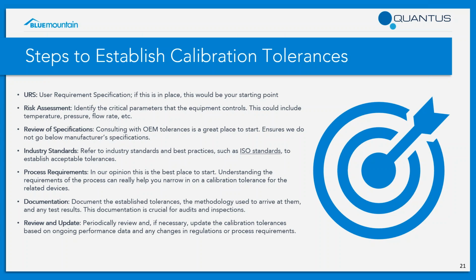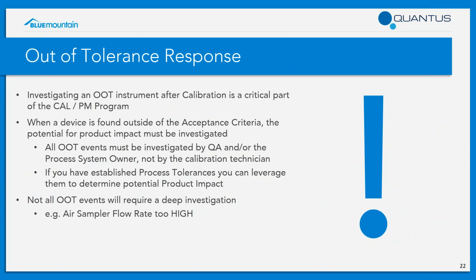If you don't have a URS or a process tolerance, have a discussion with your manufacturing team or the end user to understand where they're using that instrument and where you would calibrate it, because you do want it to be greater than the manufacturer's specified accuracy. Yeah, absolutely, Chris. That's a really good point. And as instruments are getting better and better coming from manufacturers, they're going to start bumping up against accuracies of field calibration equipment. So again, remember, they're marketing the instrument based on accuracies, so you don't always need to follow that specifically. And that brings us into out of tolerance investigation responses.